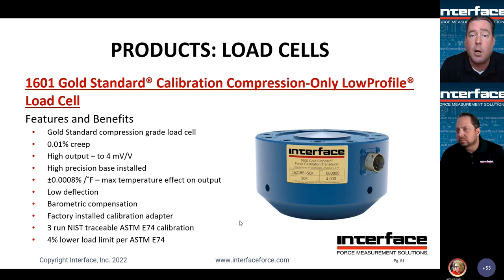So again, you could do that calibration of the standard 1600, but this does get you a lower stack height, and it does have an integral spherically radiused loading surface and installed base on it. It gets the same 3-run ASTM E74 calibration, and is also guaranteed to have a 4% or better lower limit factor. Next slide, please.